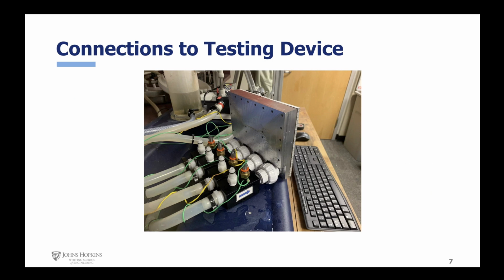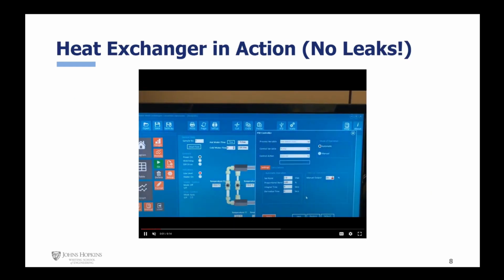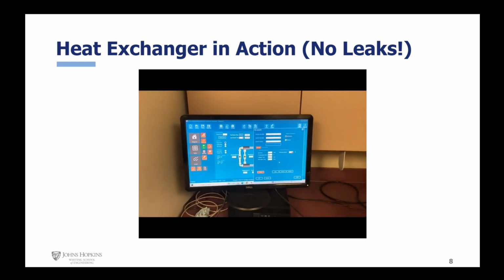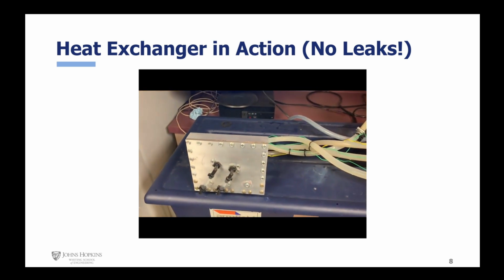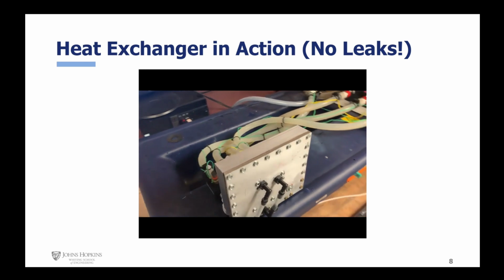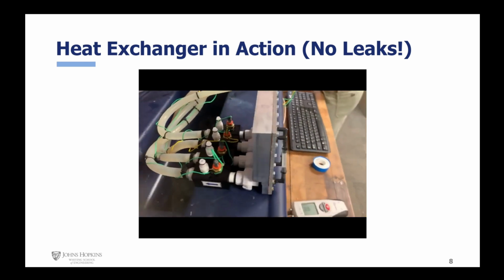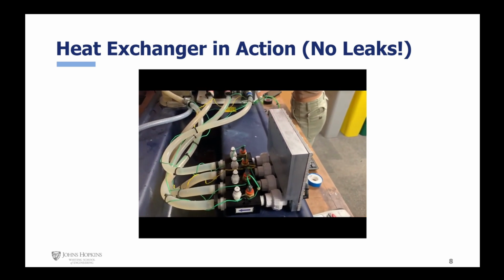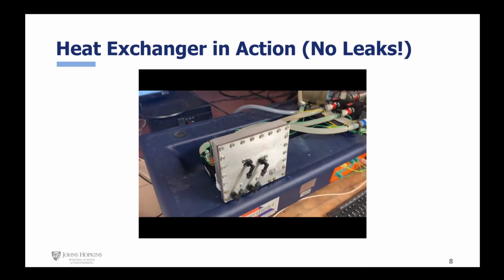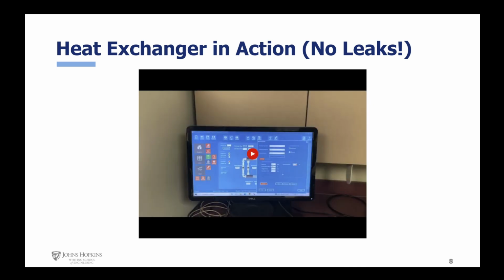Here you can see the adapters installed and our device connected to the testing unit. Here you can see our heat exchanger successfully working with no leaks. On average, we observed pressure drops of around 13.75 kPa and flow rates of 2 liters per minute for both, and temperature drops from 31.3 to 25.1 degrees Celsius and 13.5 to 7.1 degrees Celsius for the hot and cold water lines, respectively.